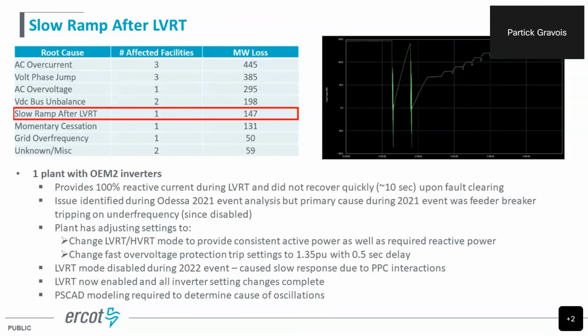A couple of things. They had an LVRT mode that was designed to take active current all the way to zero to provide 100% reactive. They were switching that mode to reduce megawatt only as much as they have to, proportional to voltage, and enough to provide that reactive, but not all the way to zero. They were also increasing their fast overvoltage protection trip to 1.35 per unit with a 0.5-second delay, which is a vast improvement over what it was before, because they had originally set it at 1.2 with 0 delay.